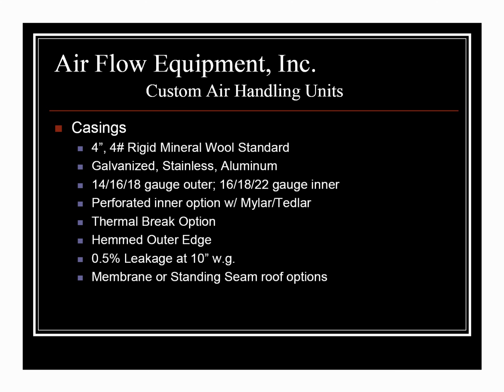We build solid inner and outer panels, and we can couple that with our perforated inner acoustical liners. When you have the perforated material with 4 inches of rigid mineral wool, you get outstanding sound attenuation that's really second to none. Foam isn't going to give you the sound attenuation of mineral wool, and neither is fiberglass. So that's something we take a lot of pride in, building a unit that's quiet, that kills the sound before it leaves the unit instead of pumping it down the ductwork.